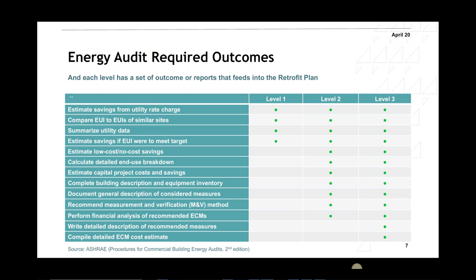We're going to see later how that looks. Estimate capital project costs and savings. How much is it going to cost you, let's say, to change the chiller? What are the savings? What is the O&M? So O&M could increase, could decrease. If you're buying a new chiller and replacing a really old, let's say, air-cooled chiller, probably the maintenance will go down. But if, let's say, you're adding an absorption chiller, maintenance will go up because you need expertise for that.